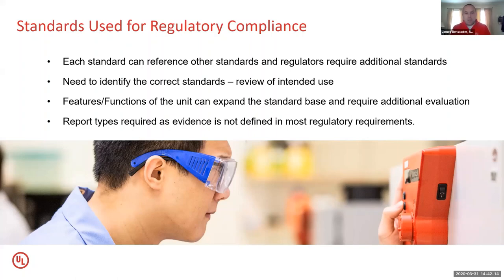Now, a key point to make out of that is there still can be other standards available to the device. And this is where you get into the non-device requirements, such as biocompatibility, different types of tubing set designs that may be called out in other standards. So really the first thing that needs to be done when you're starting to develop a product, even in a time like this, is to identify what you're going to have to comply with, because the FDA is going to expect you to have some understanding of what you're going to do to comply from a standard standpoint. And that all comes back to the intended use of the device. The more devices we see from manufacturers, the more features or functionality that they may have, and these additional functionalities can require additional standards. So in the EUA for ventilators, for example, they actually make a general reference to other standards in the 601 series. It's one of those general references because they understand that they can't cover every situation.